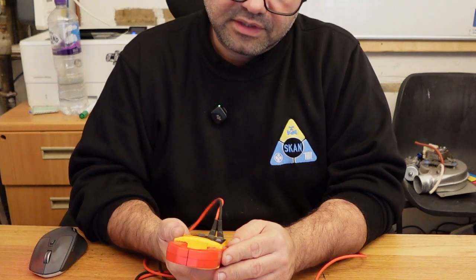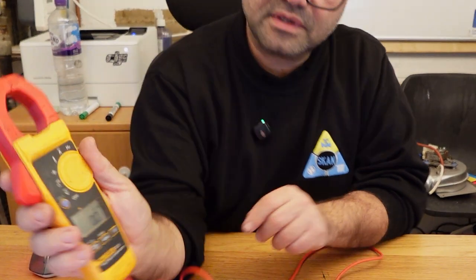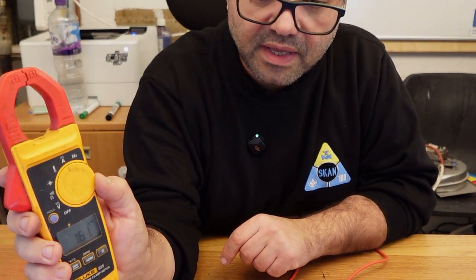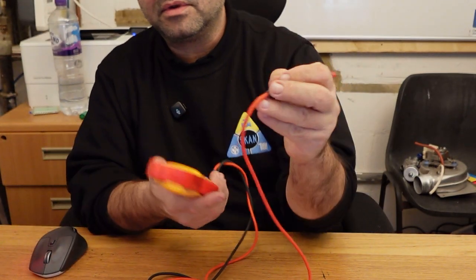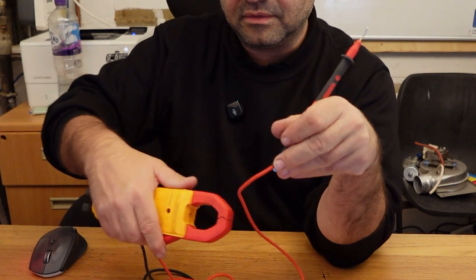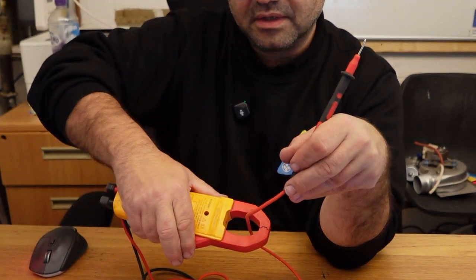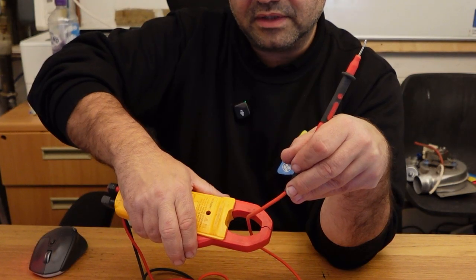The other thing we can check is the amps. If we go up here to amps, we can check DC and AC amps. The only way to do that is to clamp around whichever cable we'd like to measure, put it in here, and read the measurement.